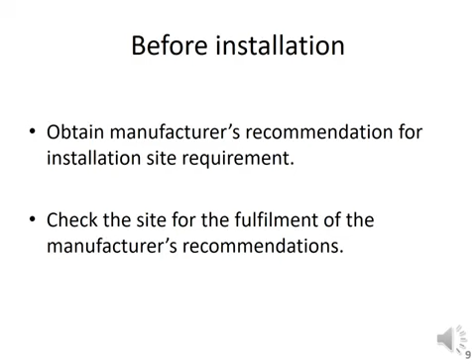So it's better to get the manufacturer's recommendation for the installation, and then check the site for the fulfillment of those recommendations. Whatever the manufacturer is recommending, check the recommendations and check that the site is fulfilling them. For example, the electricity, water, gas, plus the environmental conditions such as humidity, temperature, dust condition, etc. So you need to fulfill the recommendations. That will increase the lifespan of your machine.